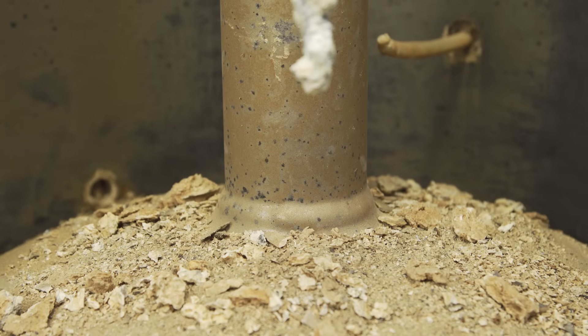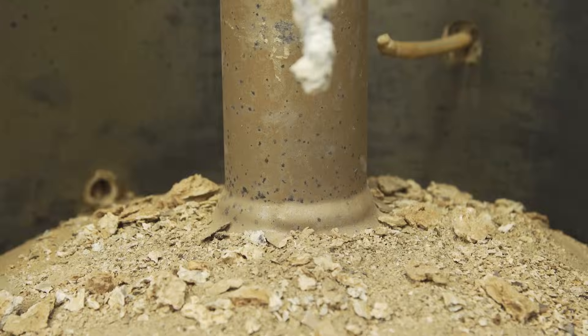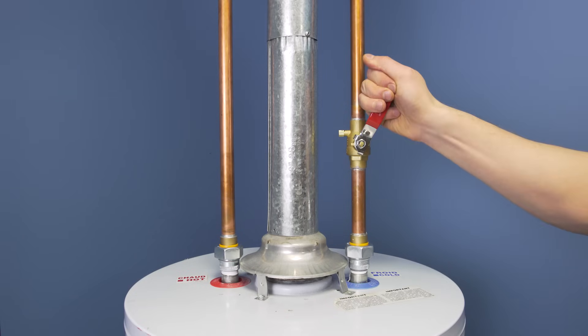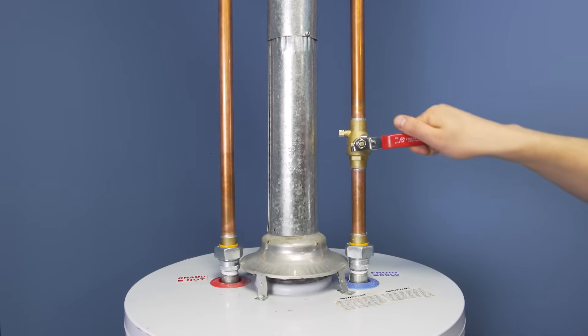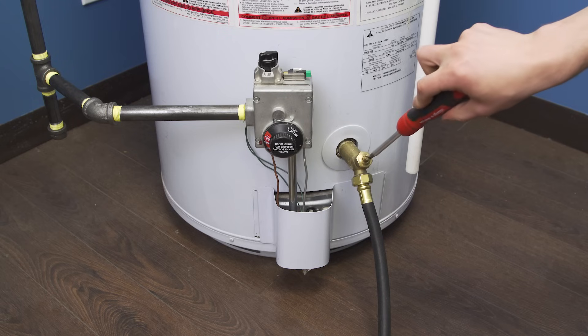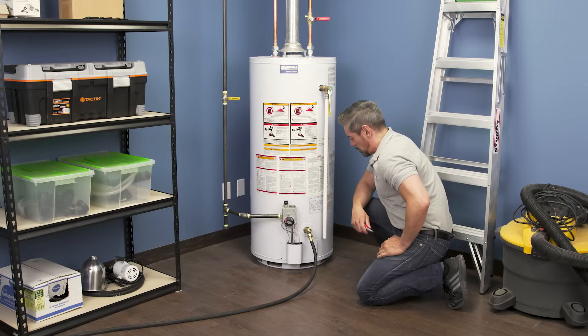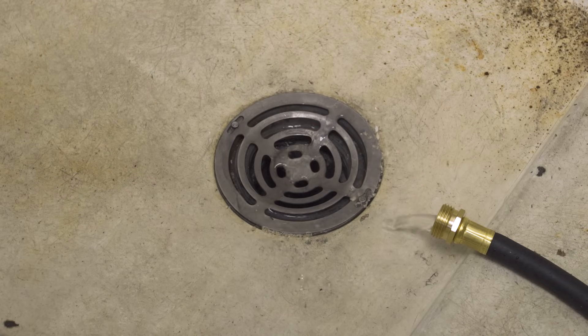Now that the tank is empty, you can do a flush to remove some of the built up sediment. Turn on the cold supply for 20 seconds to blast water into the bottom of the tank. This will agitate and lift the sediment. Now drain the water. You can repeat this 4 or 5 times as needed until the water draining out of the hose is running clear.